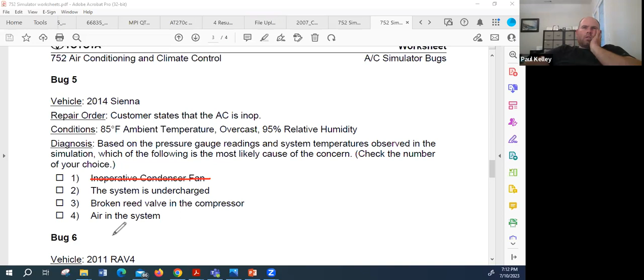What about air in the system, or the system being undercharged? It won't fluctuate that way, it shouldn't. But it could, if it sees that the pressure didn't build and it's turning the compressor off, then it's letting it run for a little bit and then turning it off. So that one's kind of interesting, actually. This is a fairly tough one. Anybody got any other thoughts?